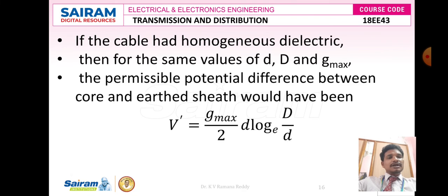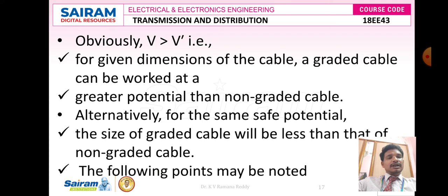If the cable had a homogeneous dielectric with the same values of d, D, and Gmax, the permissible potential difference would be V' = (Gmax/2) · d · ln(D/d). Obviously V > V', because the initial insulating material has higher electrical stress compared to outer layers for the same cable dimensions. A graded cable can therefore be worked at a greater potential than a non-graded cable. Alternatively, for the same safe potential, the size of the graded cable will be less than that of a non-graded cable.